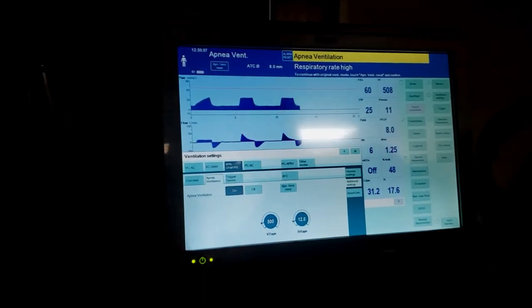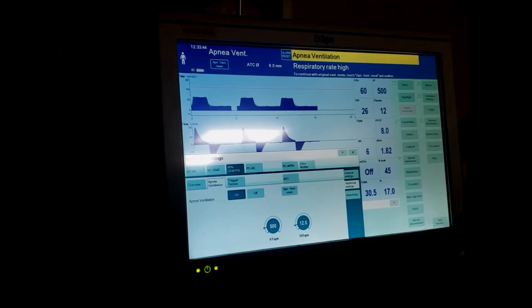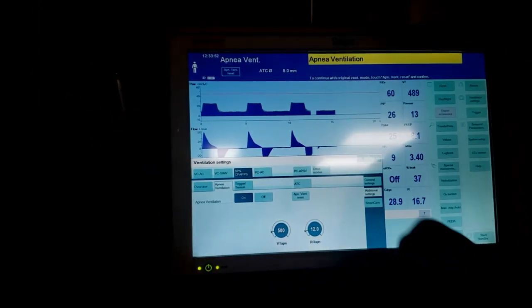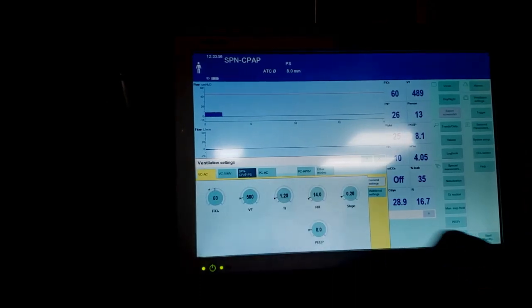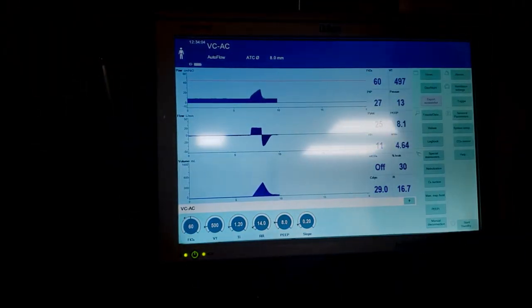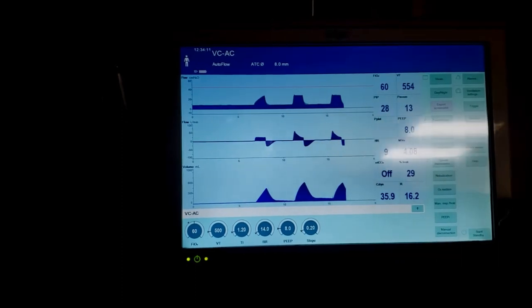If you come in the room and you see your patient is in apnea ventilation, what that means is the ventilator took over for them. So you need to figure out what the problem was. There's apnea ventilation. Let's reset that, put them back in assist control. Touch, confirm, reset apnea ventilation. Let's go back over to here, confirm. Now we're going to hit... Now we are in VC AC - that's assist control, delivering breaths. Just adjust the screen a little bit. Perfect, that's a little bit better.